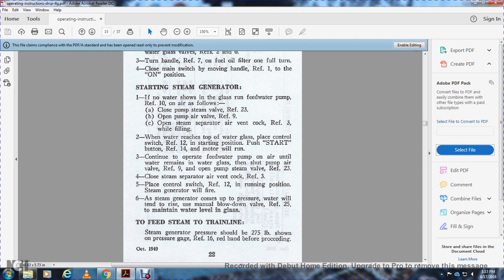3. Continue to operate the feed water pump with air until the water remains in the water glass, then shut the pump air valve, reference 9, and open the pump steam valve, reference 23. 4. Close the steam separator air vent cock, reference 3. 5. Place the control switch, reference 12, in the running position, and the steam generator will fire. 6. As the steam generator comes up to pressure, the water will tend to rise, so use the manual blowdown valve, reference 25, to maintain water level in the glass.